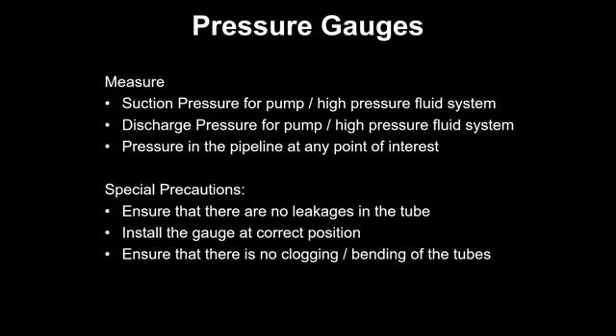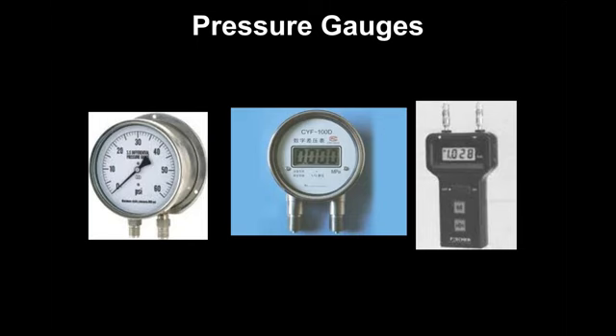Now, the basic precaution is that there should not be leakages, because if there's a leakage the reading won't come proper, and there should not be clogging in the tube. These are the pressure gauges. You would probably have seen them. Mostly we use digital instruments of this type. We have different ranges, one up to 5 kg and another up to 25 kg. So we have 2-3 ranges, and we use them depending on the application.